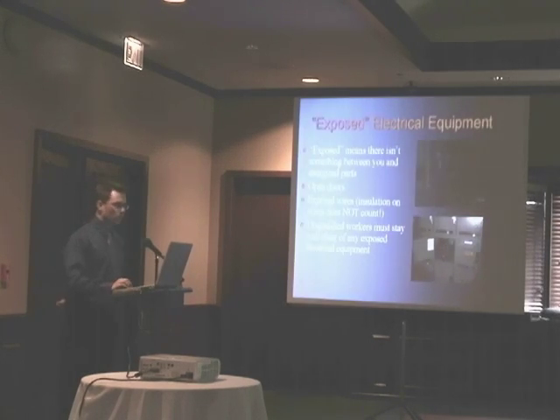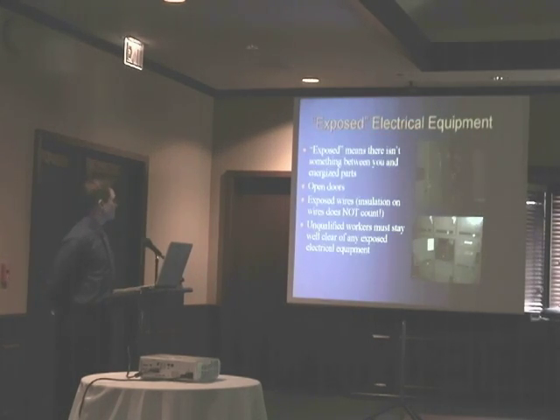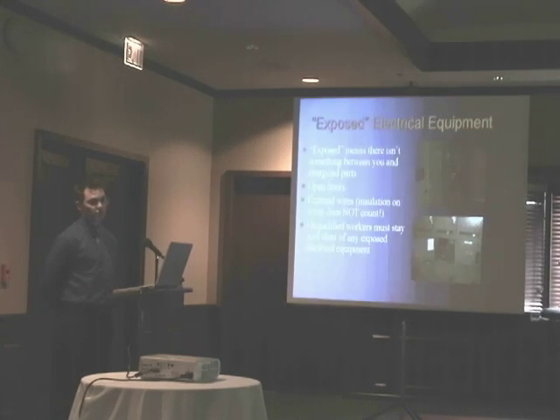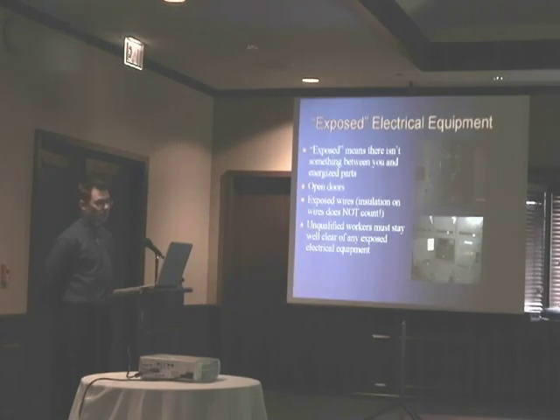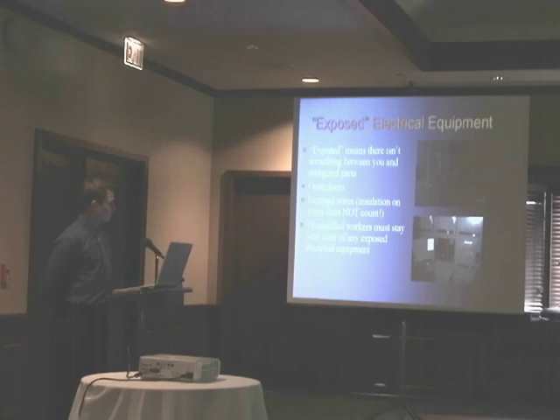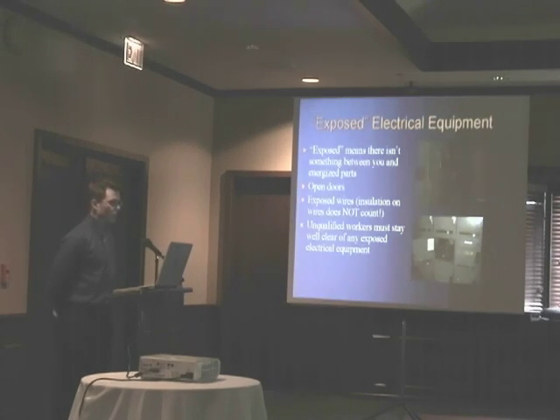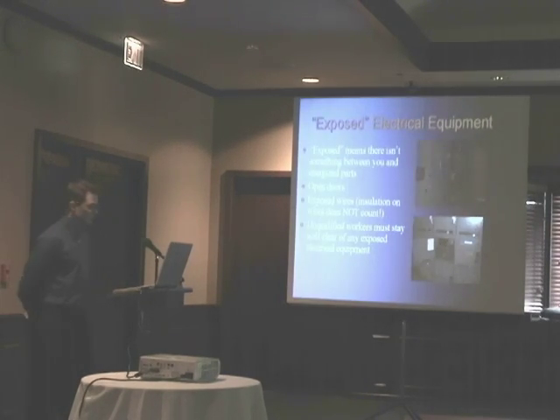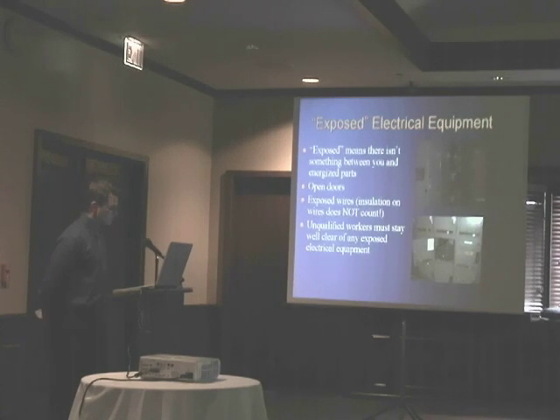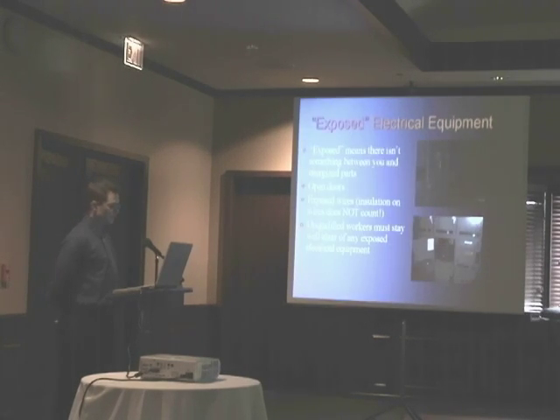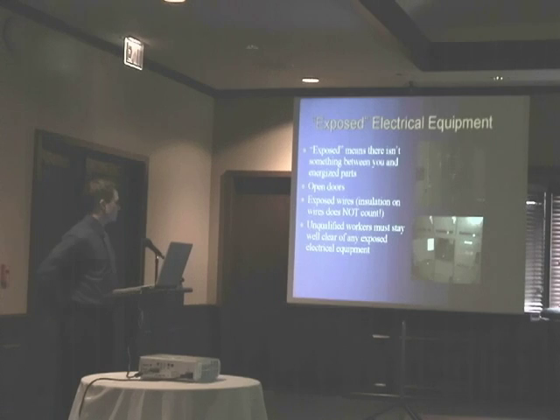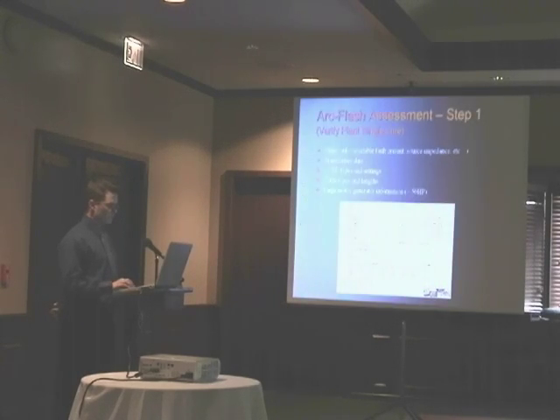Exposed electrical equipment means that there isn't something between you and the energized parts. As you can see in the top picture, that is a completely closed MCC and there are no energized parts exposed that you could accidentally touch. But in the bottom picture, with that door open, that is now an exposed energized part. Unqualified workers must stay well clear of any exposed electrical equipment.